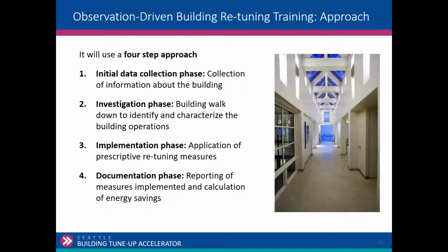Once you've identified, and I'll call them deficiencies, but let's call them opportunities, if you find equipment that isn't working, then basically repairing or placing corrective measures in place. So that's in the implementation phase. So we talked earlier about you've got an assessment phase. Does anybody do commissioning work here? So the deficiencies report or listing that. So you've done your assessment, you've identified the deficiencies. Here's what needs to get fixed, whether it's a damper, an actuator, a failed sensor, whatever that is, sequence of operation. Then you've got the implement, which is the actual implementation of that.